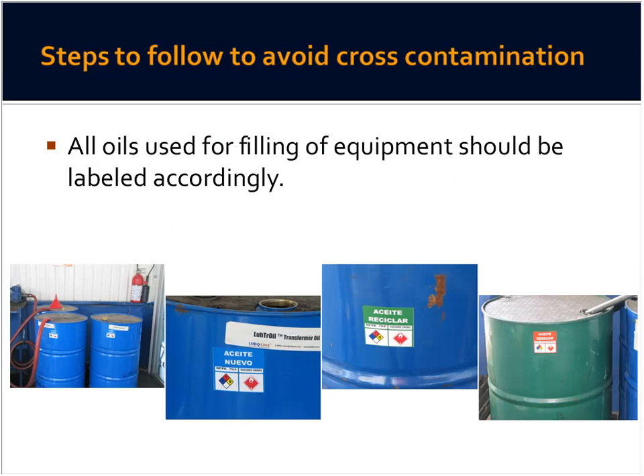The equipment and oils used in the maintenance process for refilling transformers should be labeled correctly. For instance, the second picture shows a label that says new oil, with different icons. This oil is clearly virgin oil and cannot be used if you're not sure the equipment hasn't come into contact with PCB contaminated oils.